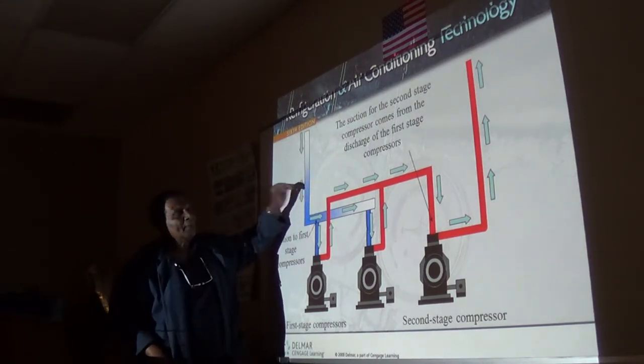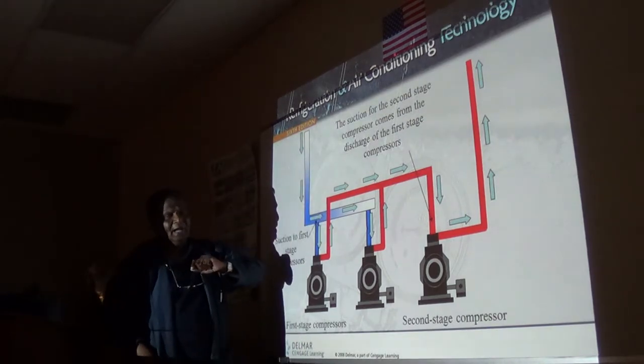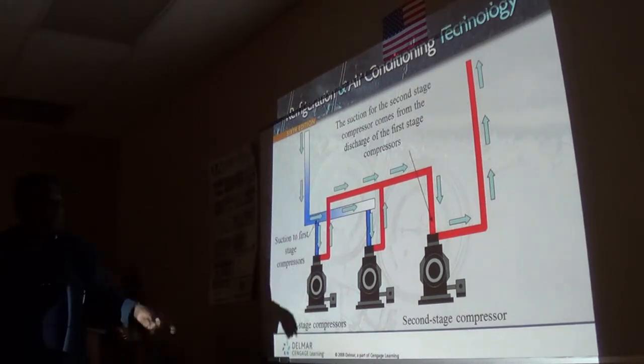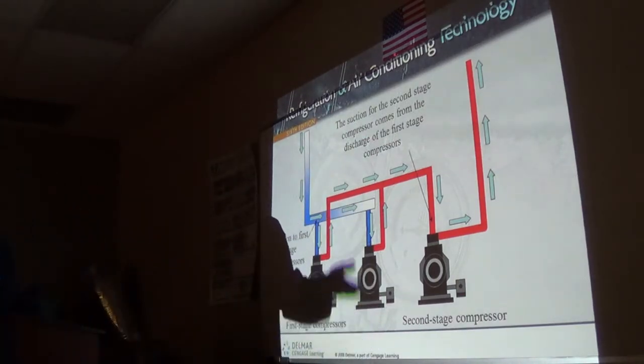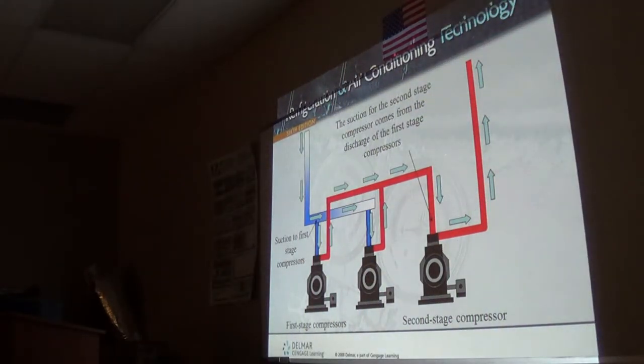Okay, so now that's zero, that's 278. I still have to go to the pressure temperature chart to find out what temperature that is. But if I put my thermometer here, and I get 125 there, I get negative 50 there, I don't even have to translate that into pressure, because I'm dealing with temperatures. So you can even charge on the temperatures. So we're not dealing with pressures really. The pressures help us to translate it into temperature.